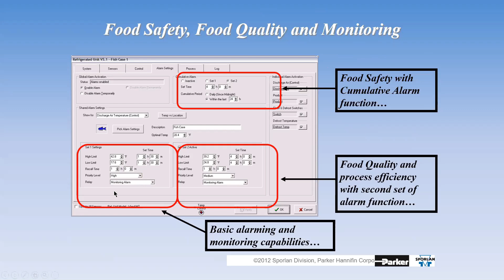So let me show you what I'm talking about. This graph here, this is alarm set point 1. Now, you see this, guys? That's my actual temperature. It's not good. It's not riding close to the blue line, which is the set point. And it never turns red. Never turns red because I've never gone outside the parameters. You with me? But 5 minutes here, 15 minutes here, a minute, 5 minutes, 20 minutes, an hour, and finally I've triggered the cumulative. And even though my primary alarm never went off, you see what happened here? My cumulative alarm went off.